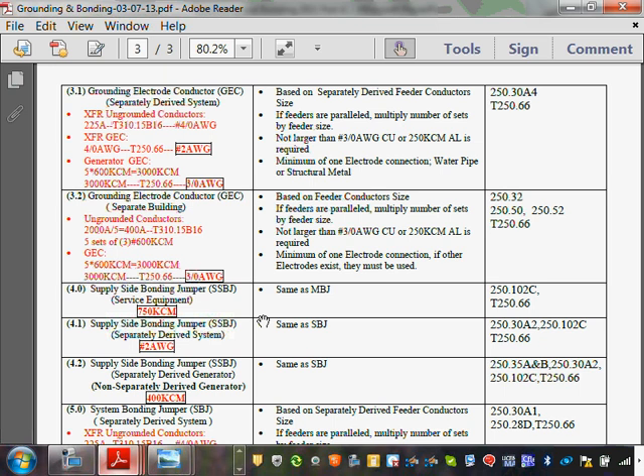So if I'm using one big wire and go to conduit 1, 2, 3, 4, 5, 10 to ground, that's the size of this wire. Now that would be dumber than a rock to do, right? If you want to take a home run from each conduit to the ground, 10 conduits, 10 conductors to the ground, then you size it based on a 600 kcmil, which would be a smaller conductor, more manageable.